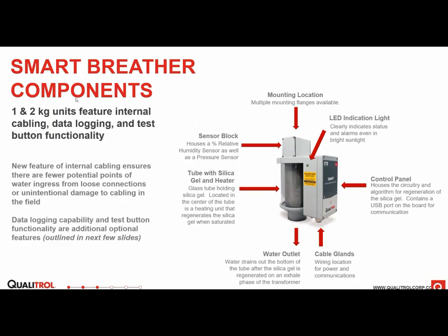So here's an overview of the new Qualitrol Smart Transformer Breather. So here you can see each of the physical features of the breather. So the first thing that stands out is that there's no longer any external cabling. And that's a big feature because sometimes the external cabling can be affected by, say, an animal chews a cable, and that causes a short, or one of the connection points on the cable becomes loose and it lets moisture or water into the electrical enclosure, which is never good.